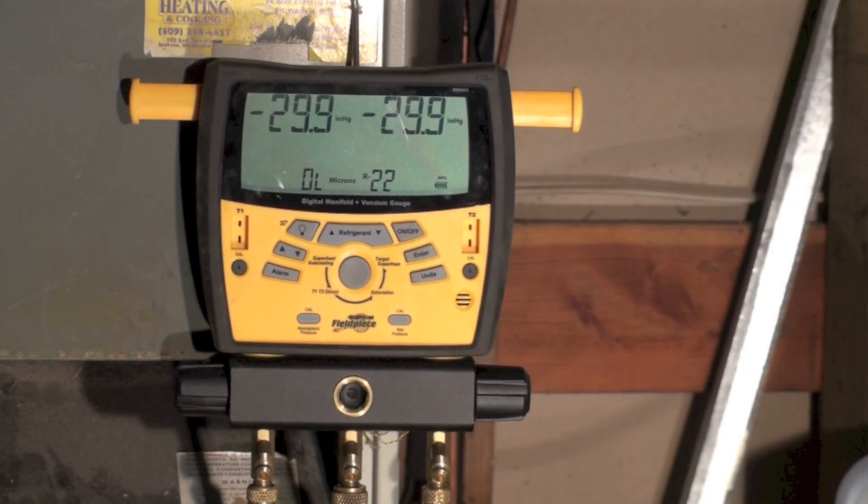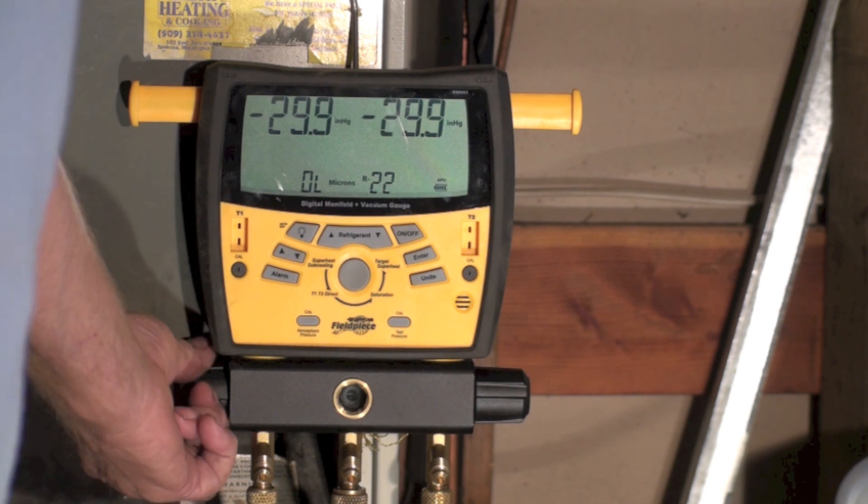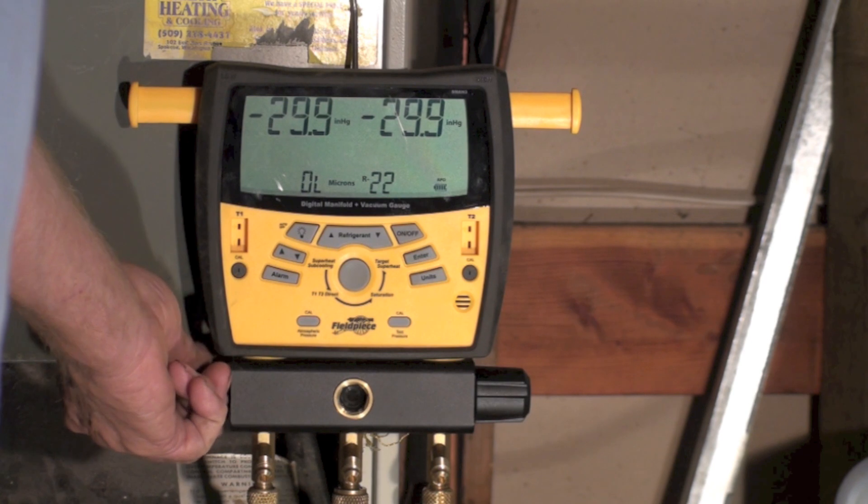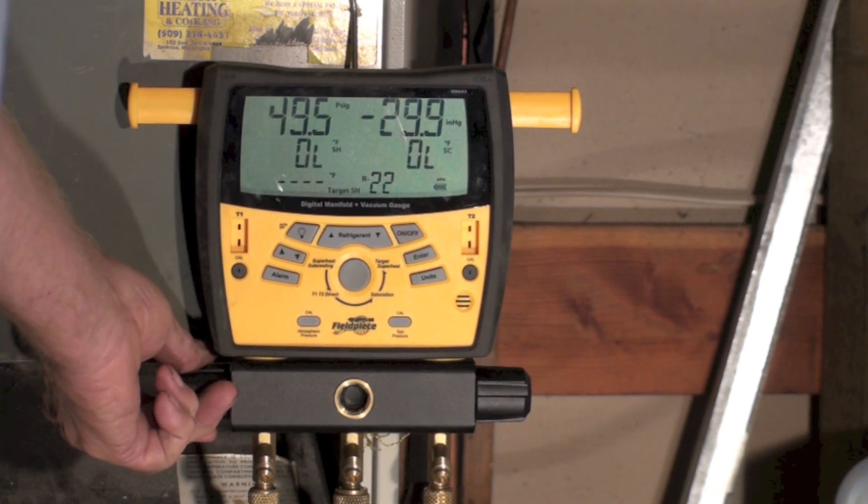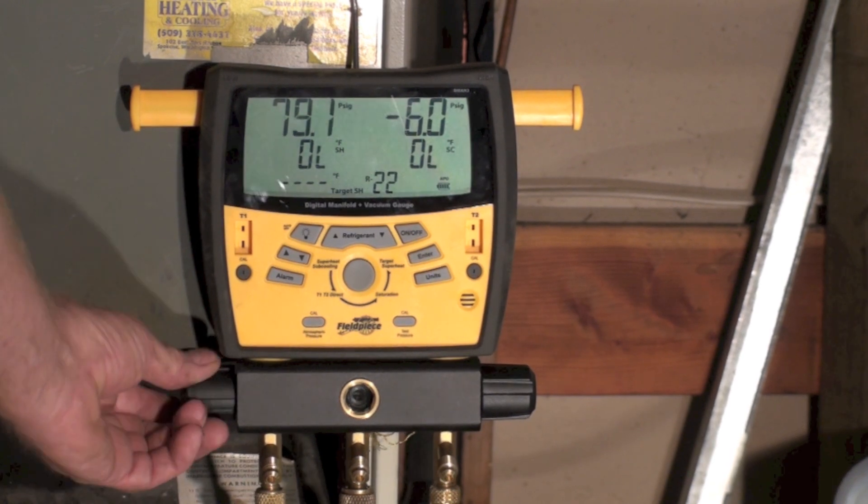So now what I'm going to be looking for is a positive pressure in the system, depending on the size of the system, 5 to 10 pounds PSIG. So I'm going to go ahead and open up the low side of this. You can open both sides if you wish. It really doesn't make too much difference.